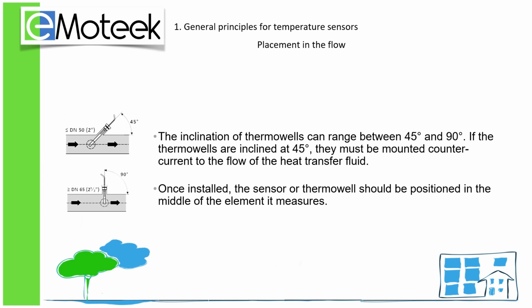For diameters less than 50 millimeters, incline the thermal wells by 45 degrees. For larger diameters, the sensor should be perpendicular to the pipes. Once installed, the sensor or thermal well should be in the middle of the element it measures. That's all you need to know about installing temperature sensors on piping.